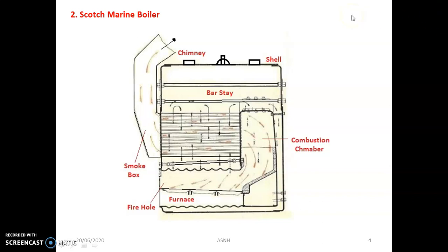Keep in mind that the components used in all boilers are the same but the arrangement is different. In the Scotch marine boiler, you can see from the image that it consists of multiple furnaces — here three furnaces are used. Each furnace has its own combustion chamber on its back side. The main specialty of the Scotch marine boiler is that it has multiple furnaces in the range of 3 to 7, and for medium capacity, generally 2 to 5 furnaces are used.